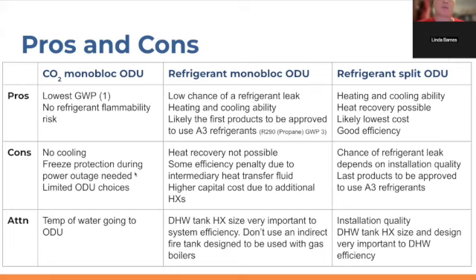And then they can also be installed with freeze protection valves. These are special valves that, if they detect the temperature is below freezing, will open up and start to drip water. Dripping water helps prevent freezing. So oftentimes they're installed with that feature.